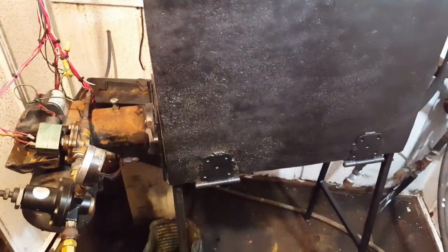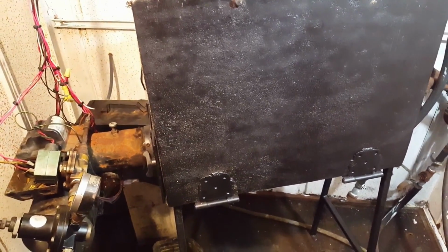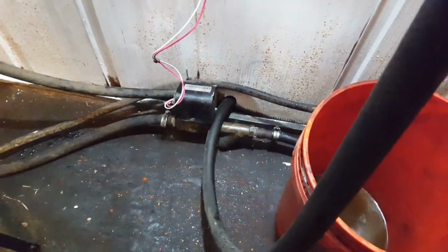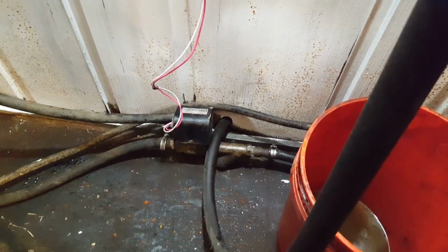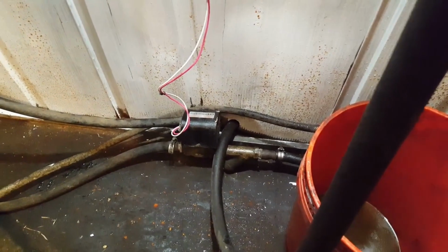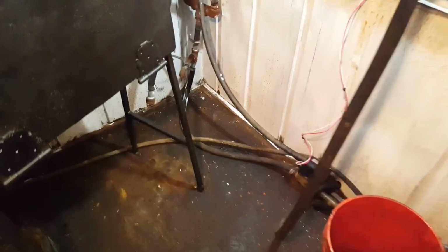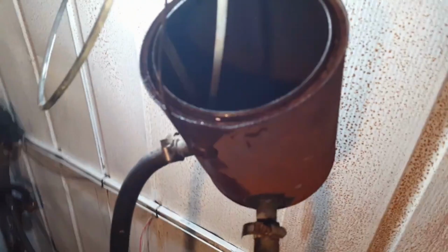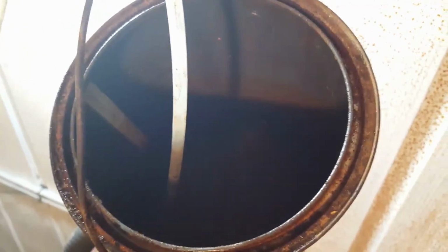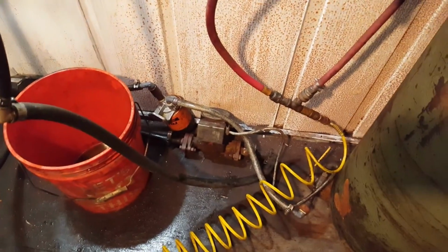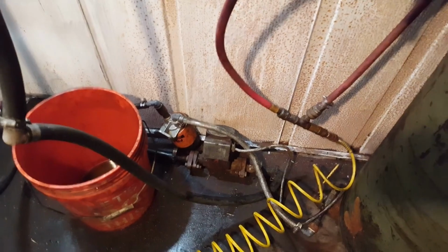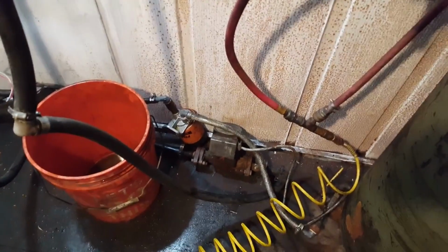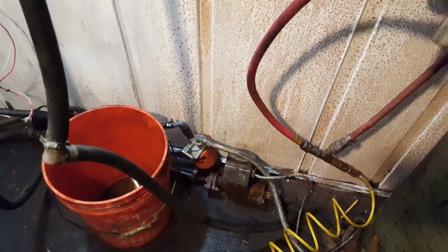While I was standing here thinking, I just hit the e-stop button. It pulled it off, circulating pump came on, I heard the flow switch click on, and about 5 seconds later it clicked off. I thought, that's kind of odd. So I took the top off the reservoir, and that water is barely moving. I believe that's the issue - I'm just not moving any water. I've got to figure out if it's the pump, if I'm stopped up somewhere, or what's going on.